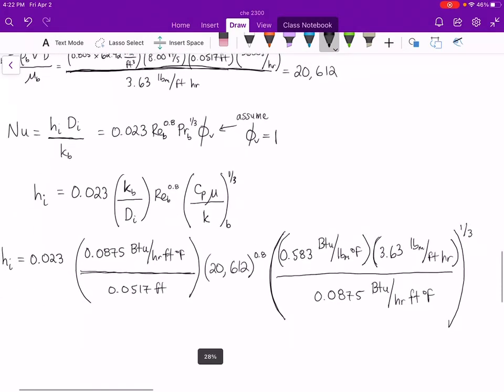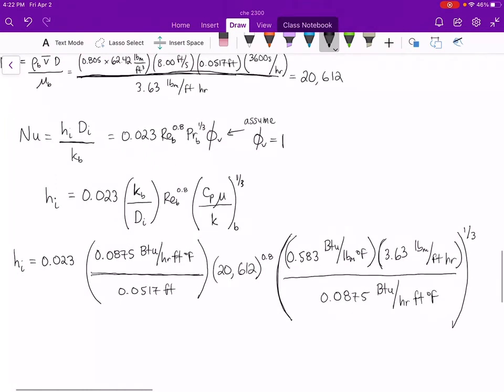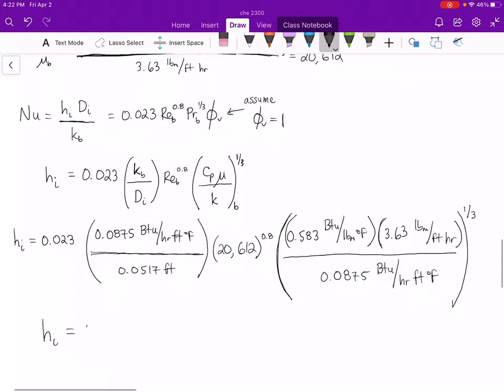Let me zoom out and get all of that on one screen. That is our Sieder-Tate equation completely filled in with our parameters. Performing that calculation, we get a convective heat transfer coefficient on the inside of the pipe of 318 BTUs per hour foot squared degrees Fahrenheit.